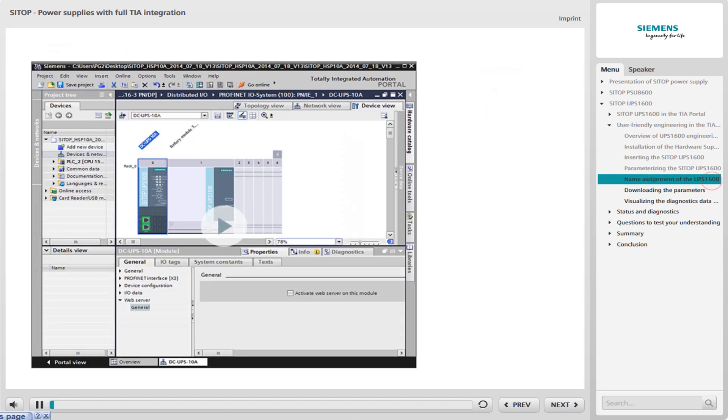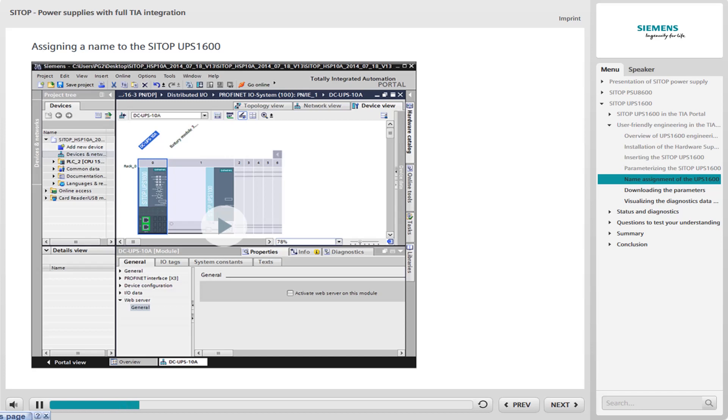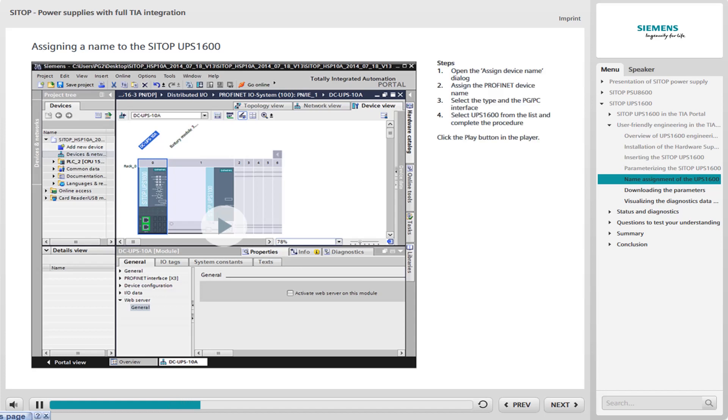In the delivery state of the UPS 1600, only the factory settings are loaded. For this reason, the PROFINET device name must be assigned to the UPS 1600 before use. Initially, you are in the device view of the UPS 1600. To assign a name, work through the following steps. First, open the Assign Device Name dialog.